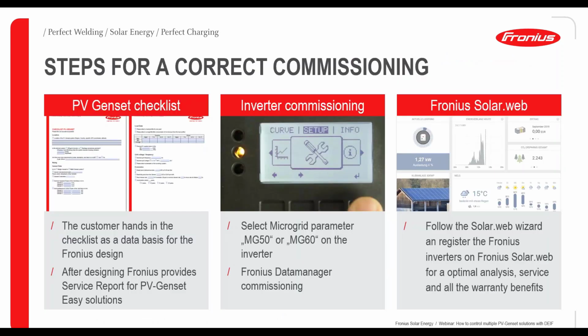Okay, so one last slide here. What are then the following steps for you as installer to do, or as system designer? You can send in a checklist to Fronius, also to DEIF, of course. By doing this, we can first of all give you a service report. If it is a multiple diesel generator system, we forward this to DEIF, of course, so that they can then apply the system.